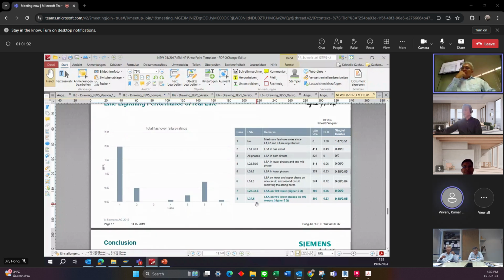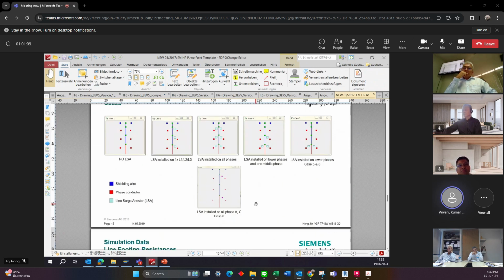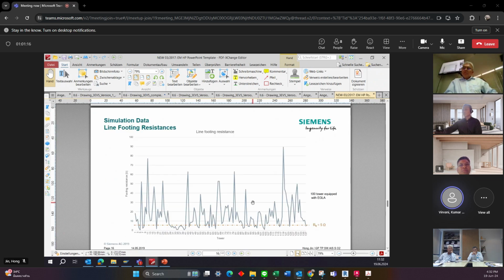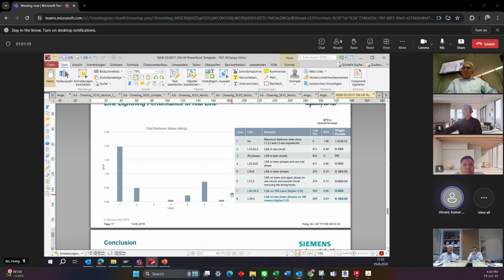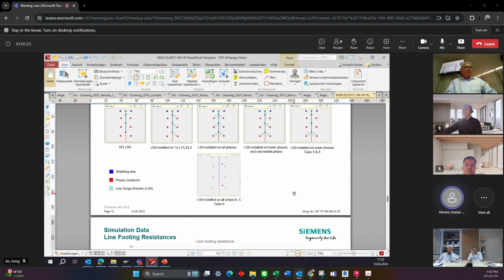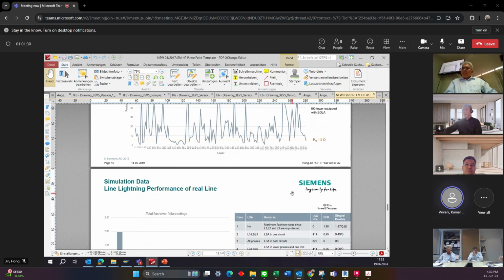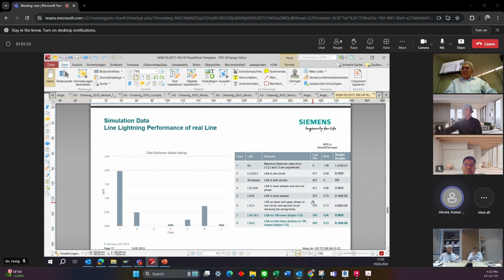And as also mentioned earlier, in a double circuit line, if we install the arrester on a single side, all 3 phases, it will definitely protect against double circuit failure, but we can't be sure whether it will suffice the system requirement. Sometimes when there is a high tower footing resistance on some of the towers, we need to install the arresters on both bottom phases of the tower, just to ensure that we protect that tower against back flashover, because back flashover will affect the bottom phases of the double circuit line.